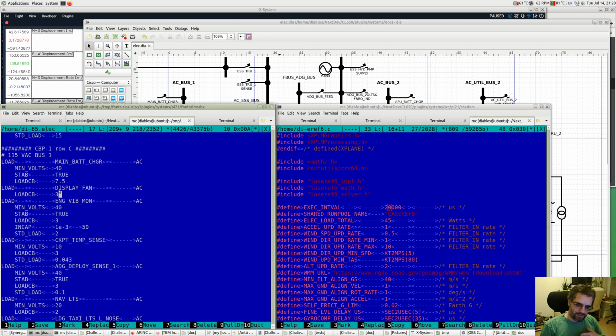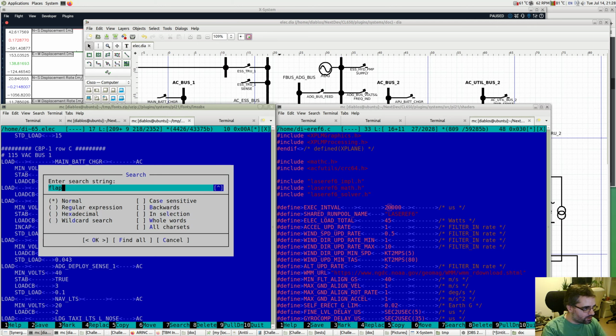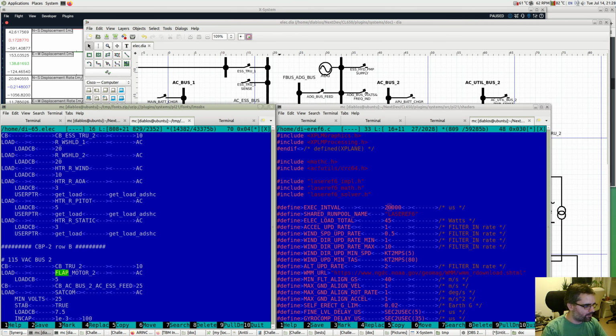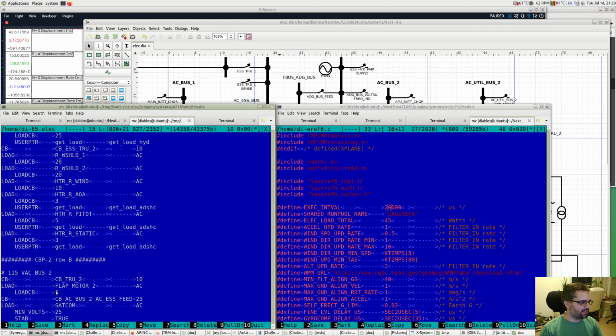Because it is a non-stabilized power supply, it draws a fixed amount of current, and whatever current it gets at whatever voltage becomes its output power. It drives things like flap motors, for example the flap motors in the flap electronic control unit, or flap drive unit. Looking at the flap trim indicator, flap motor 2, you can see the flap motor is an AC source, running on 115 volt AC, with only a 5 amp breaker, no stabilized power supply.